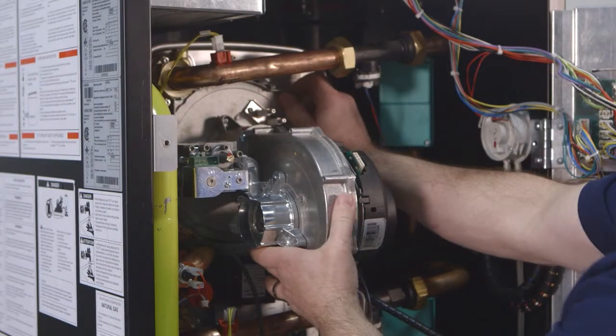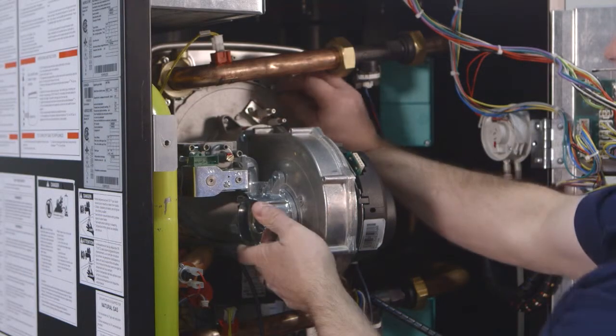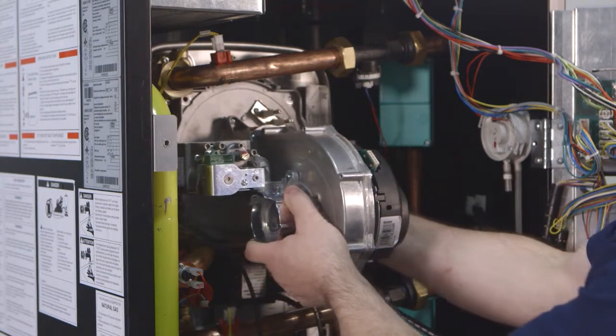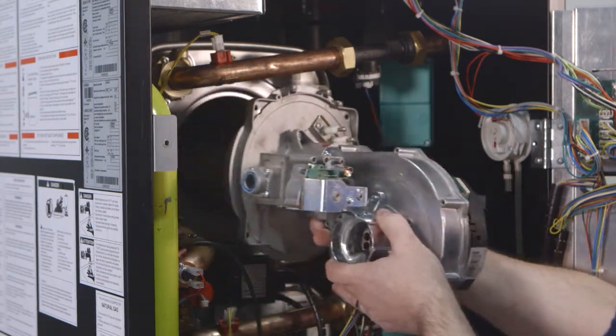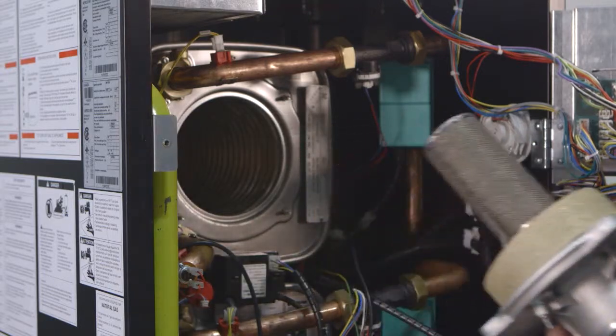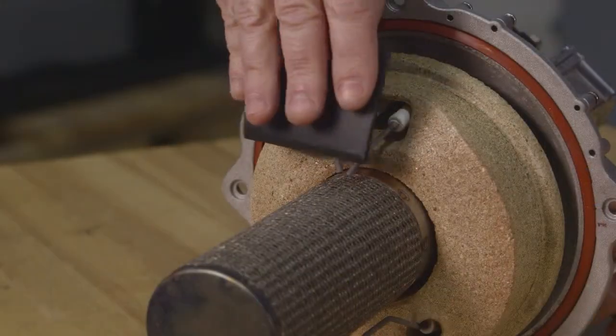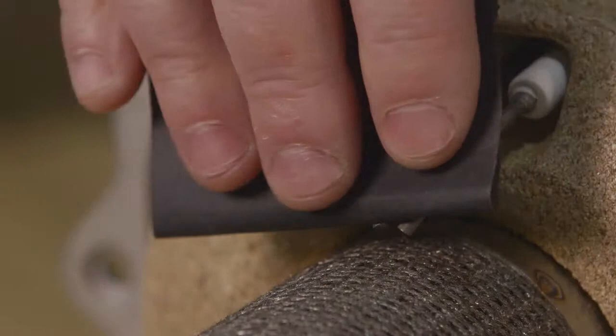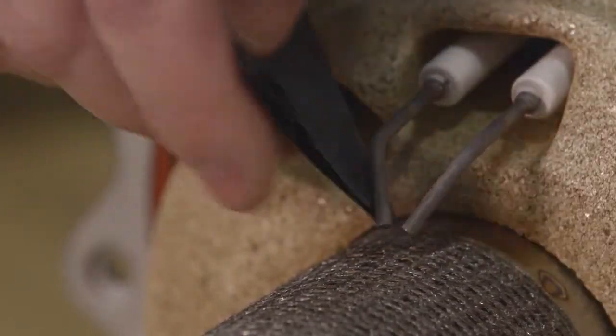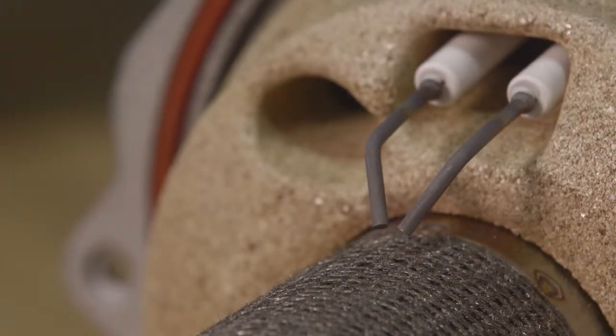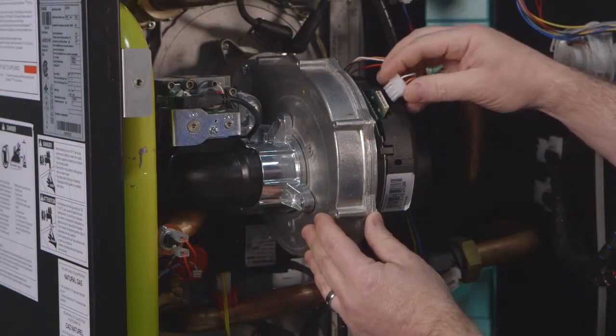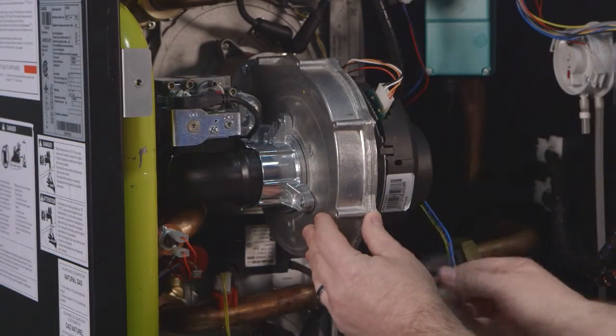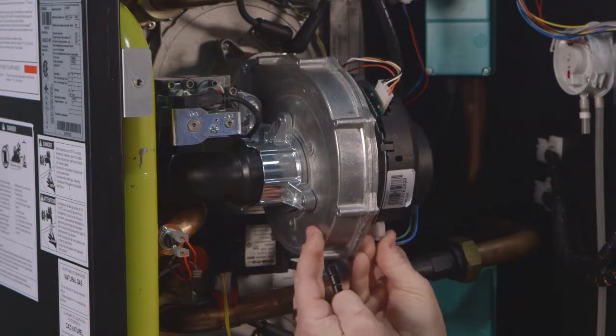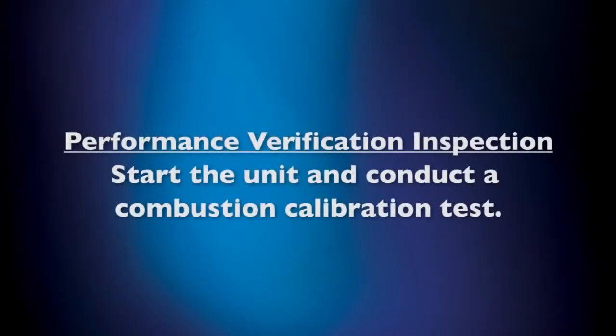First, remove the fan burner assembly unit. Remove any deposits accumulated on the ignition and flame sensor electrode using sandpaper. Check the positioning of the electrodes. Finally, reinstall the fan burner assembly back into the unit. For a performance verification inspection, start the unit and conduct a combustion calibration test.